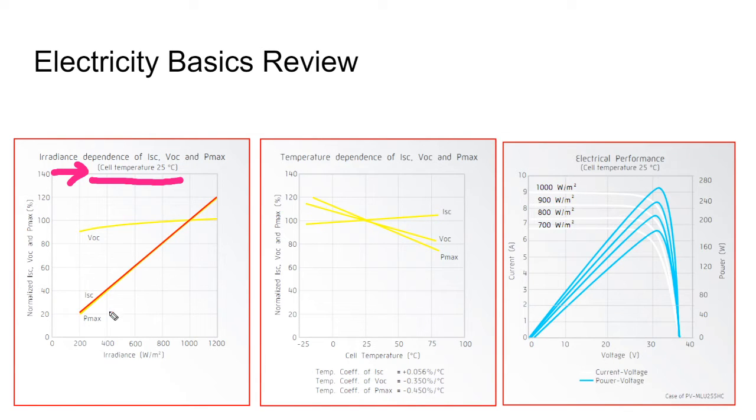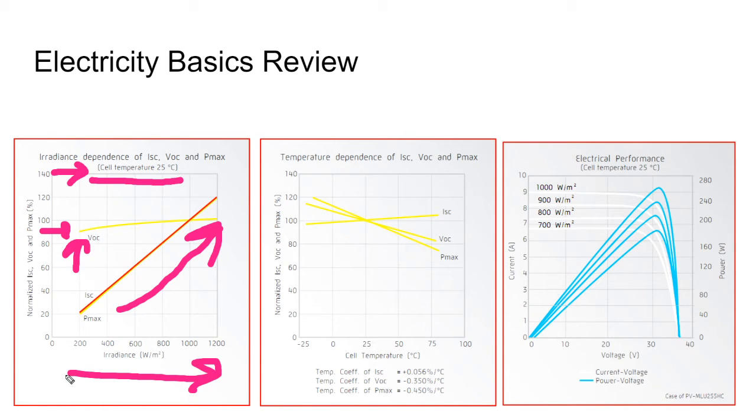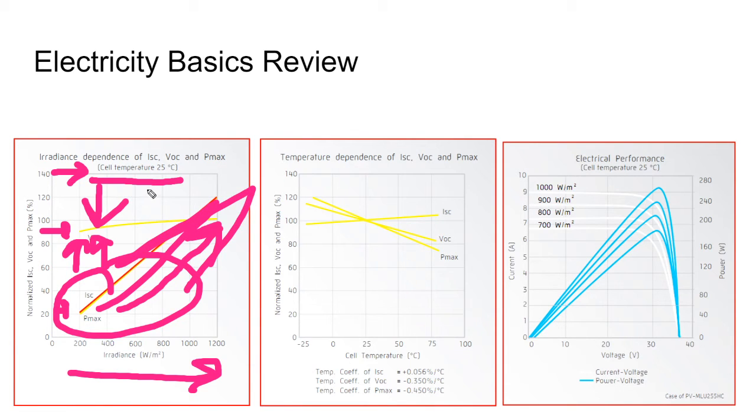What we see is with more irradiance, our power is increasing. What we also see is even with a little bit of irradiance, our voltage starts out with high voltage and low current. And so on a sunny day in the morning, the voltage is still going to start climbing. And when the array turns on and off, it's still going to be operating at higher voltages. It's more the difference between an array performance on a sunny day versus a hazy day is there going to be more or less current, much more than more or less voltage. Voltage starts off high in these systems.